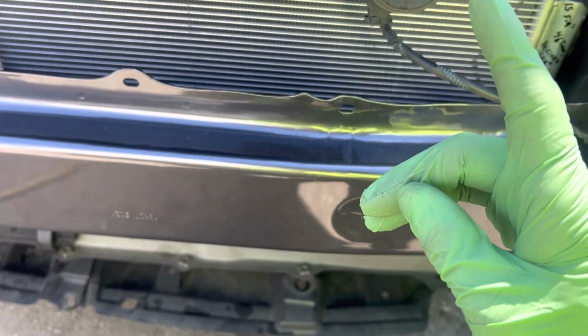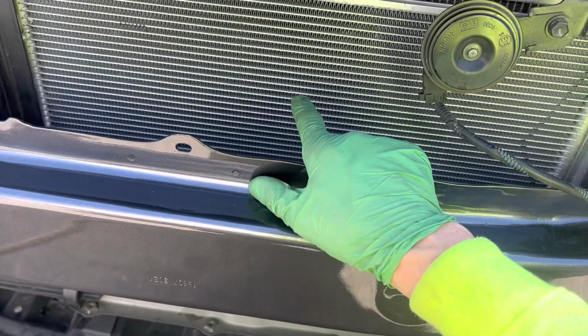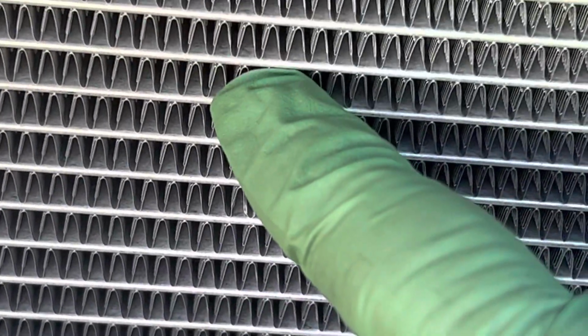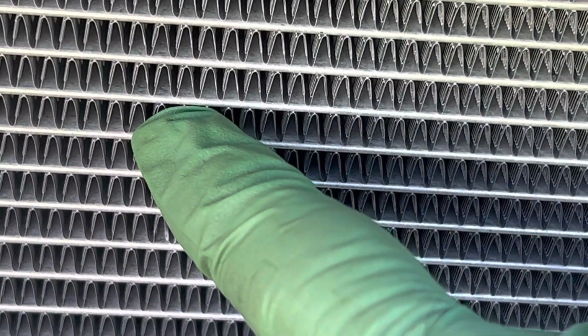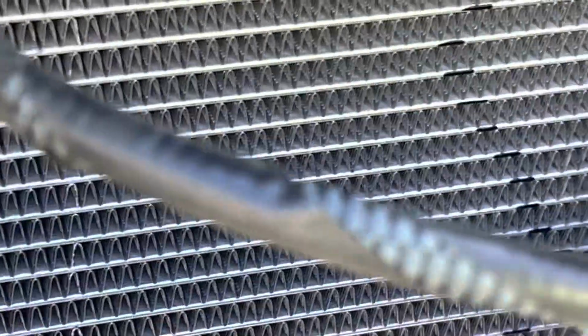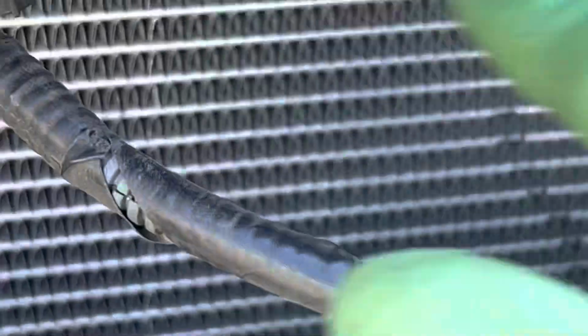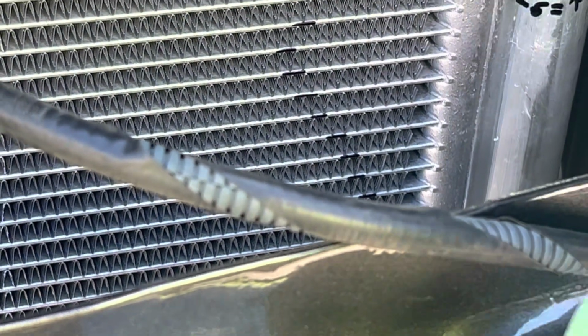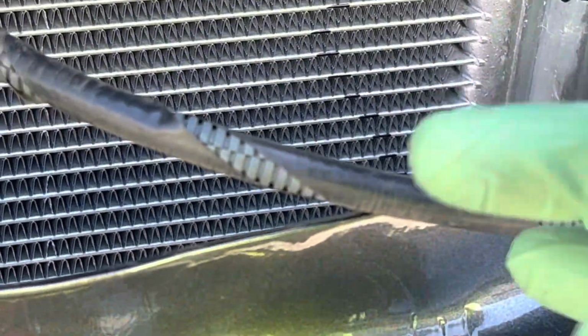And in my previous condensers, I explained, instead of having 21 fins per inch, this only has 15 fins per inch instead of 21 fins per inch. That's what I was writing down as I was copying over there. Instead of having 50 tubes, refrigerant passage tubes, this only has 46. And instead of having a 1.33 diameter receiver, it has a 1.26 diameter receiver.